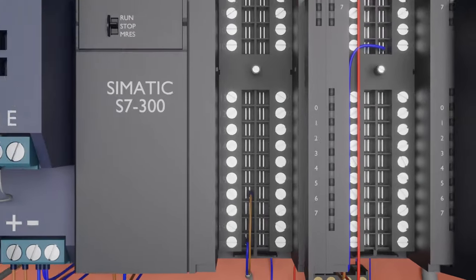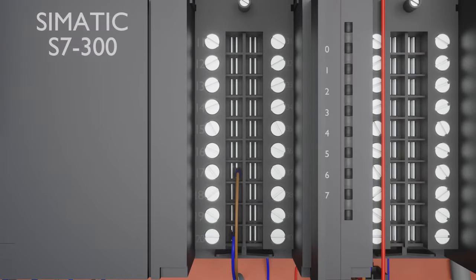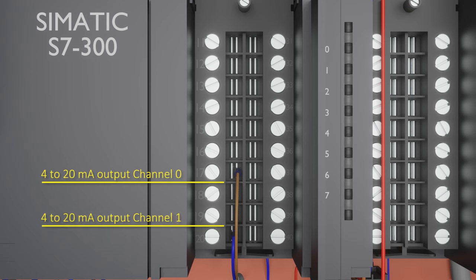This particular CPU has two analog output channels. Terminal 17 is the current output for channel 0, and terminal 19 is the current output for channel 1. Terminal 20 is the common terminal for these analog outputs.